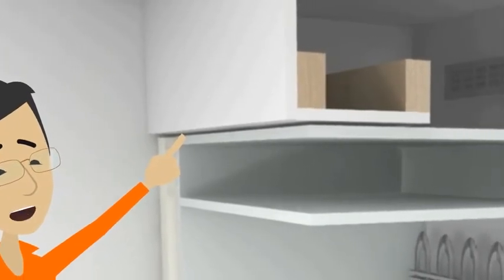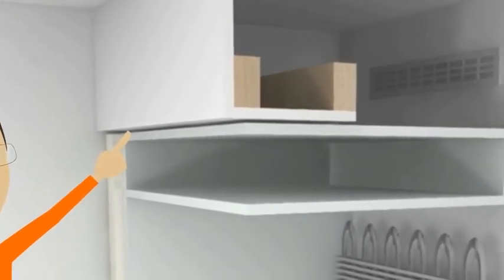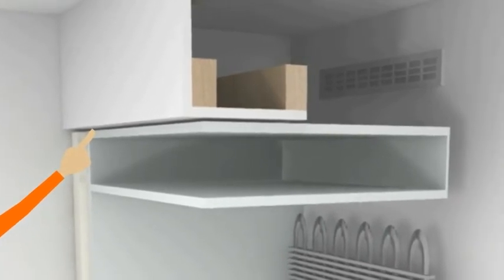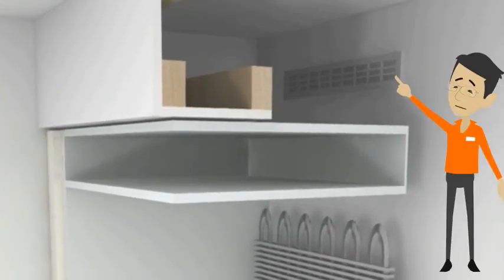If you would like to design with a 5 millimeter gap over the units, then you will need to do either of the following. Place a 200 centimeter squared vent behind the bulkhead which will exhaust the air into, for example, a utility room.